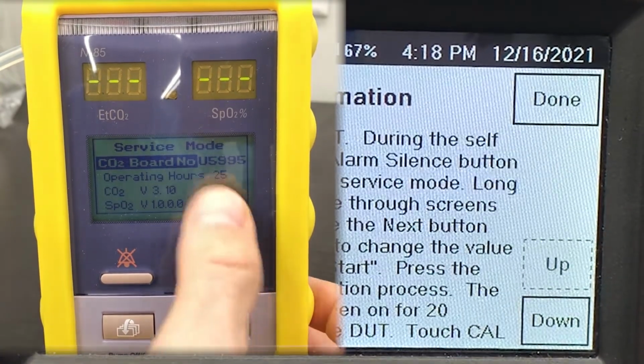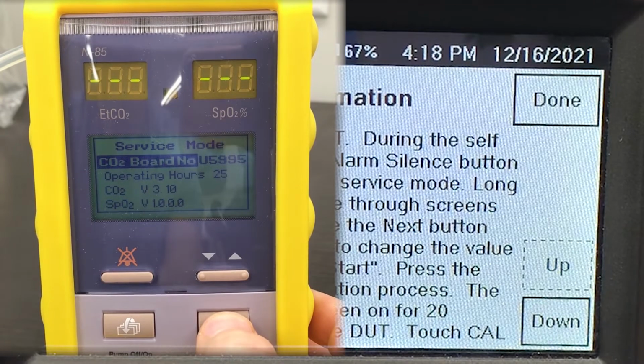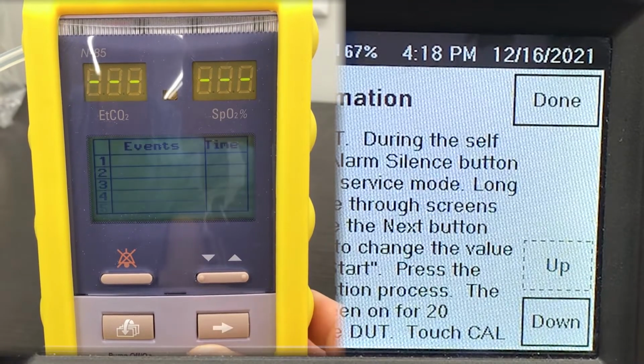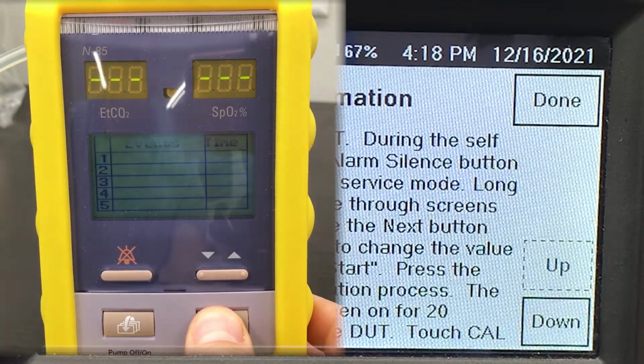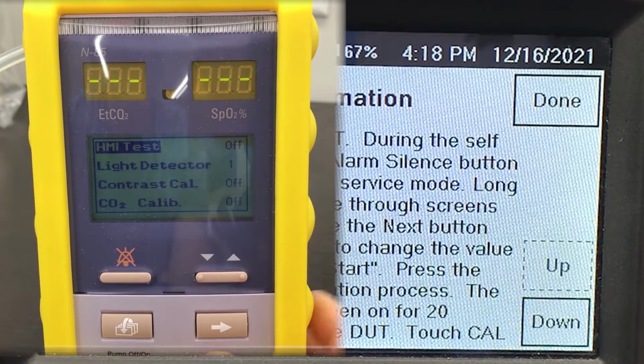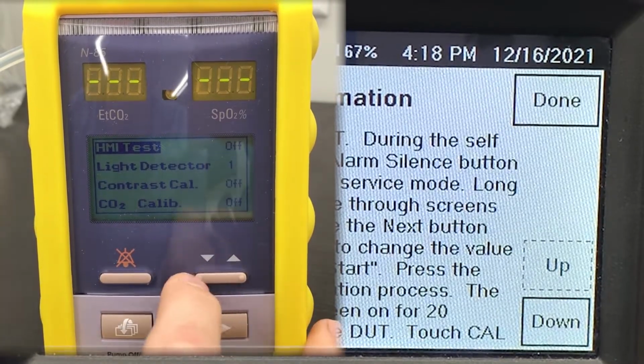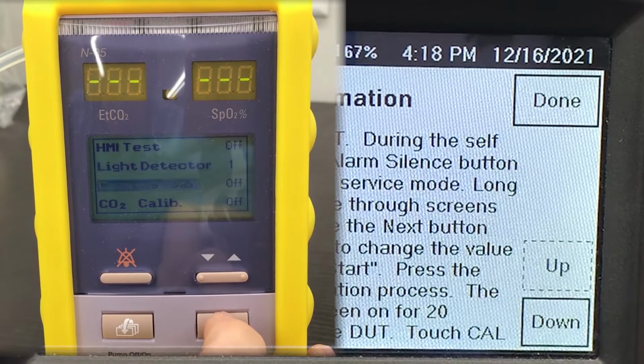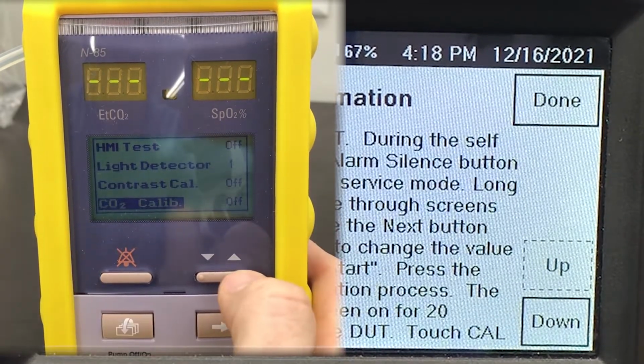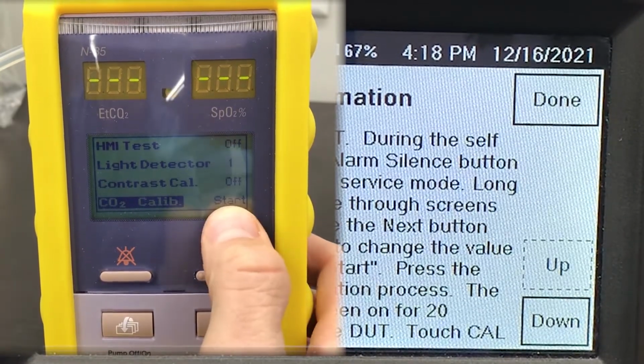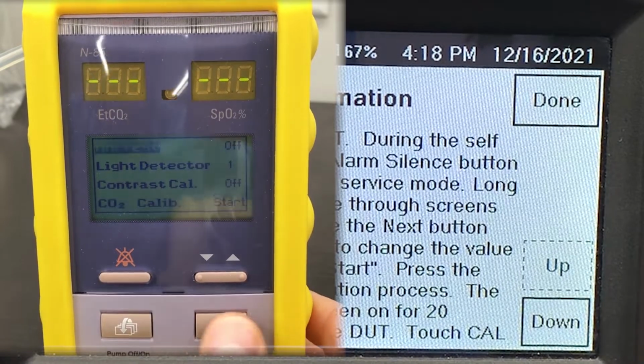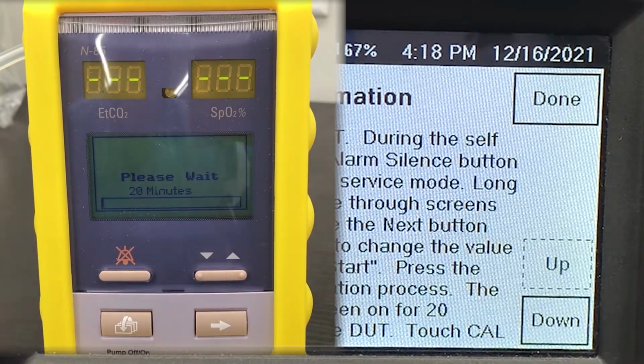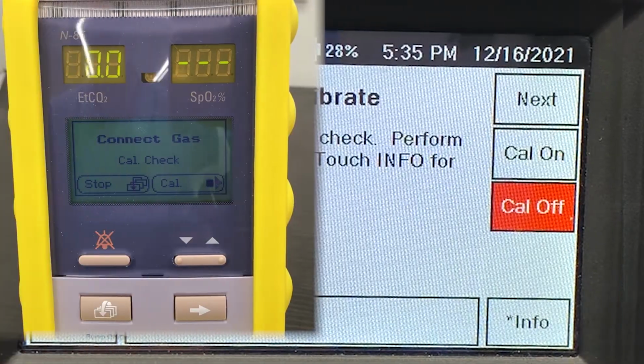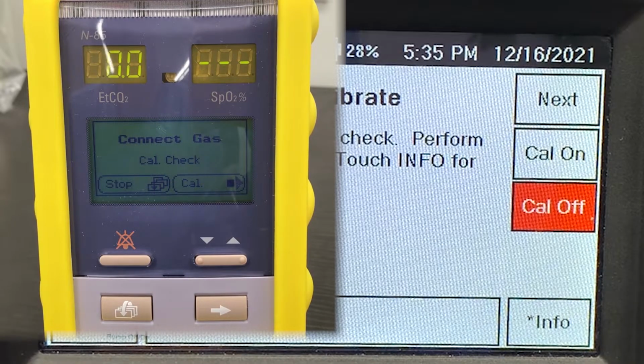Then we just long press the next button once, twice. Now you see here a CO2 calibration. Then we use the down arrow or the next arrow to get to CO2 calibration. Use the up and down arrow to put that to start. Then when we press next, we'll start calibration. It always makes you wait 20 minutes because it wants to make sure that it's fully warmed up. After the monitor has warmed up, it'll say connect gas.